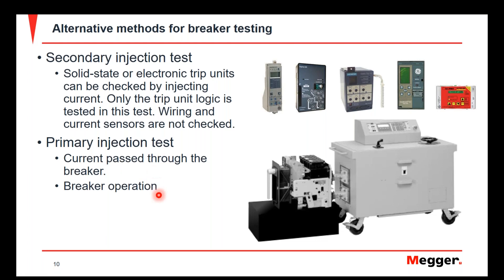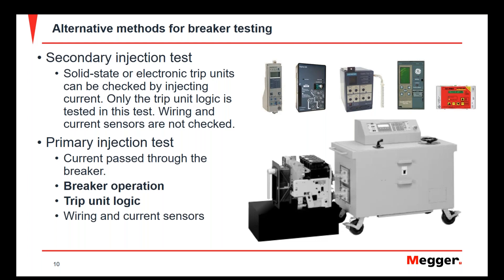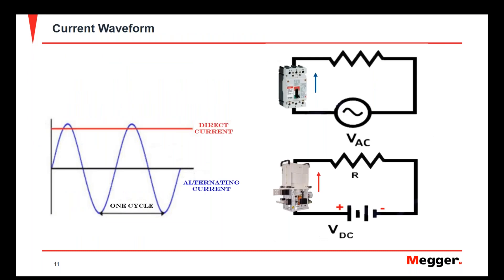Whenever we do primary current injection, we're testing the breaker's overall operation as well as checking the logic of the trip unit to make sure it's communicating properly with the other elements of the breaker, such as the current sensors and the wiring associated with the trip unit. In other words, a primary current injection test is a complete system test to verify that it's going to operate the way we want it to, ensuring reliable operation. We also need to consider the waveform we'll use for these primary current injection tests.